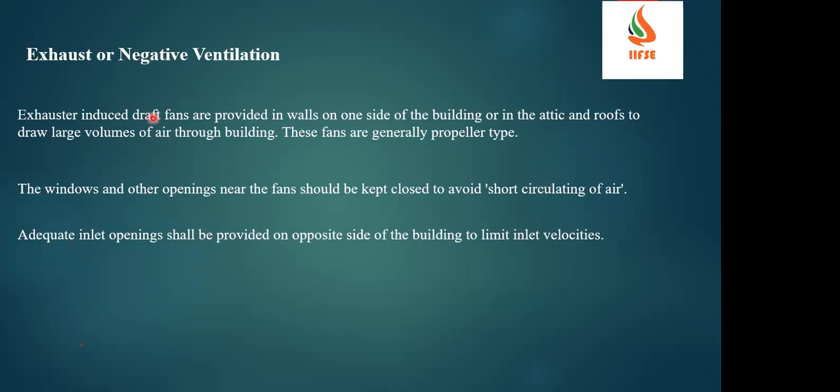Here you have to observe, to draw a large amount of air from the building. These fans are generally of the propeller type. So what will happen here? They will take out the air from inside the building. And the windows and other openings near the fans should be kept closed to avoid short circulating of the air. How will it get short circulated? For example, this is my building.